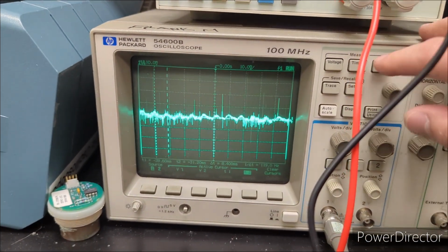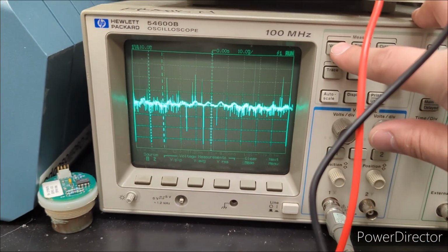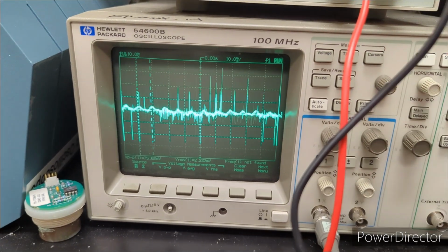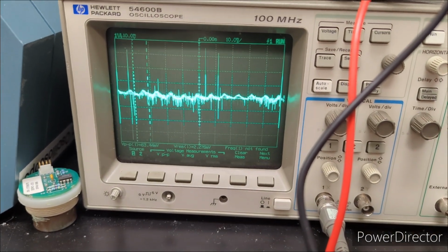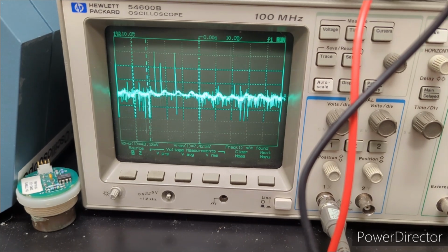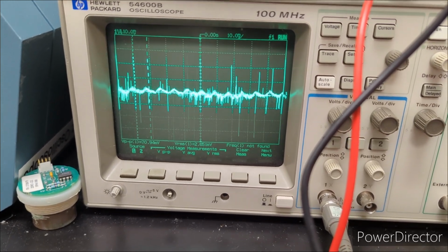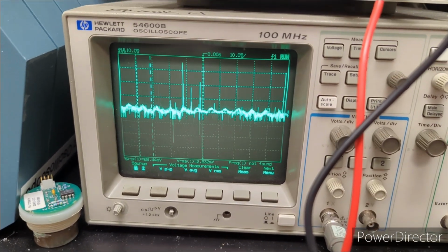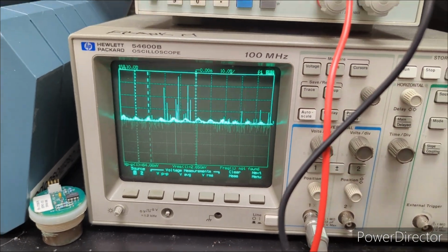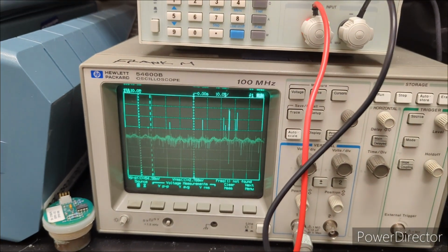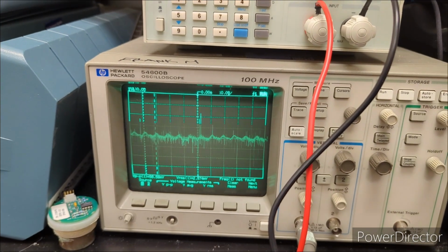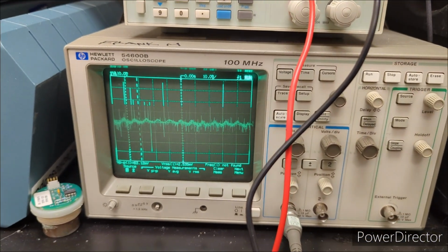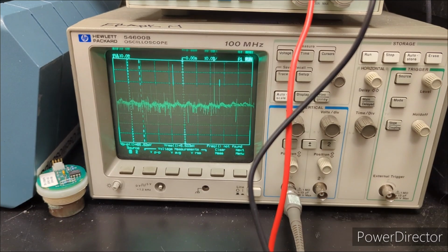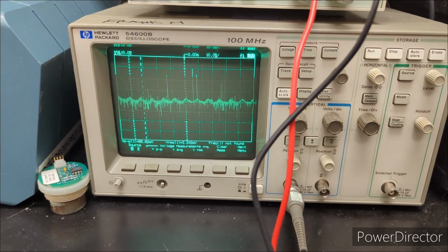If we go to voltage, so yeah, we're getting some peak-to-peak measurements upwards of 60, 70 millivolts. Now, there is a specified bandwidth for this measurement. I believe it's 20 hertz to 20 megahertz. So right now, I've got the scope bandwidth limited to 20 megahertz.